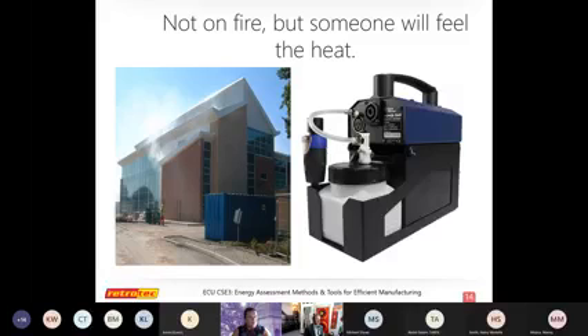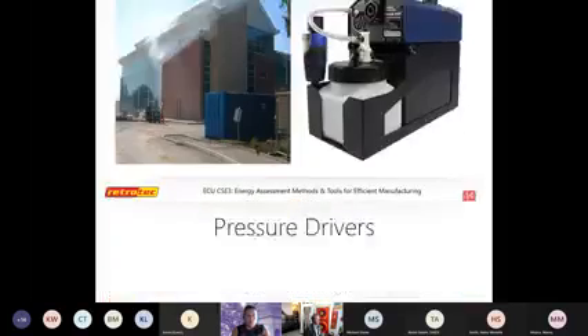Fog is another way we can do this. If you ever do this on your building, call the fire department and let them know, because someone will call and think your building is on fire. We've had that happen before. But you can take theatrical fog machines and these blower door fans as you're running the tests. If you're pressurizing the building, you can put some fog along the roof line and then step outside and see where that fog is escaping from to see where some of your air leaks might be occurring. You can also find the source of some roof leaks this way as well. We've also done that. So the tricky thing about air is it's invisible. So any way that we can make that air visible is going to be a nice, easy way for us to track down where those problems are occurring to fix things up.